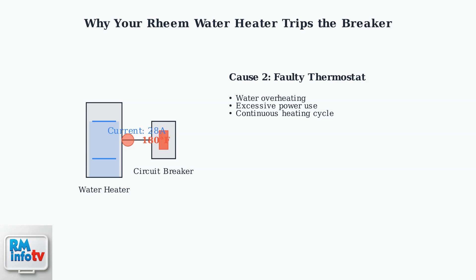A defective thermostat can cause the water to overheat beyond safe limits. This leads to excessive power consumption as the heating elements work harder than designed.